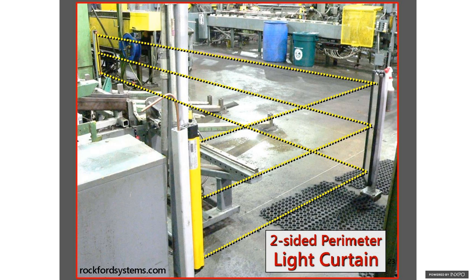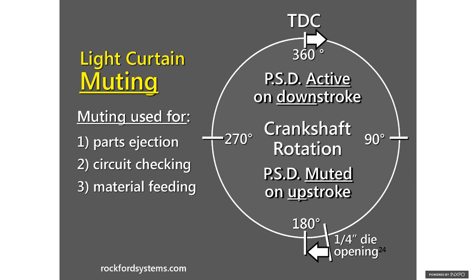How about a three-beam light system where it's going around the corner with a mirror? Yeah, you can do that, keeping in mind that you want no more than 24 inches space between the light beams, and at the bottom, you want to try to maintain no more than 6 inches opening. So a three-beam system works well for doing that and going around the corner. You can do two things with light curtains. You can mute the light curtain, that is to turn it off during the non-hazardous portion of the cycle, assuming the machine it's applied to has a non-hazardous portion of the cycle. And you can also blank, which we're going to talk about on the next slide.